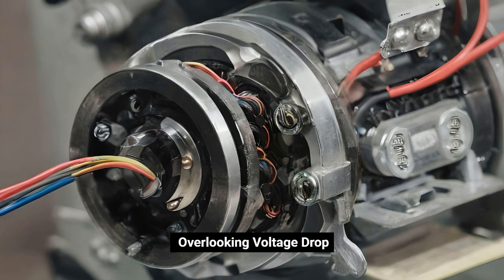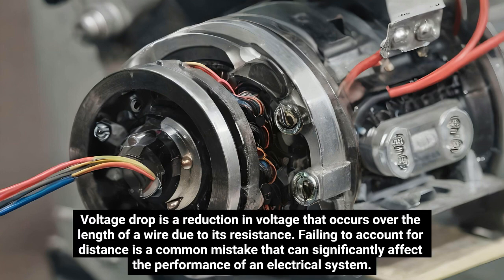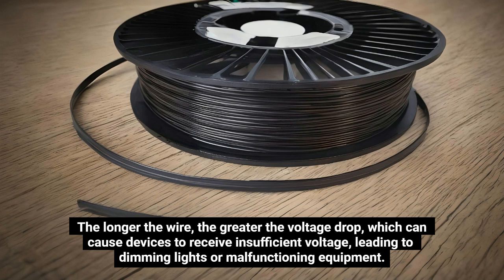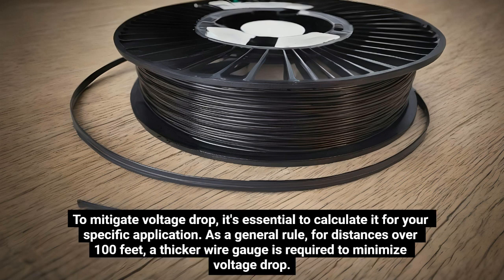Overlooking voltage drop. Voltage drop is a reduction in voltage that occurs over the length of a wire due to its resistance. Failing to account for distance is a common mistake that can significantly affect the performance of an electrical system. The longer the wire, the greater the voltage drop, which can cause devices to receive insufficient voltage, leading to dimming lights or malfunctioning equipment. To mitigate voltage drop, it's essential to calculate it for your specific application. As a general rule, for distances over 100 feet, a thicker wire gauge is required to minimize voltage drop.